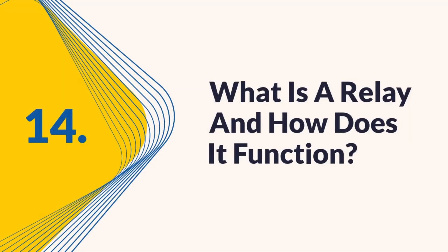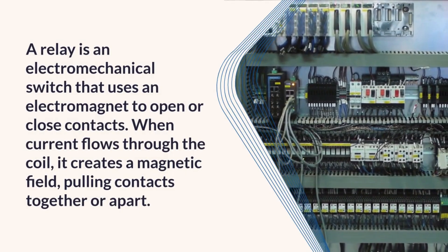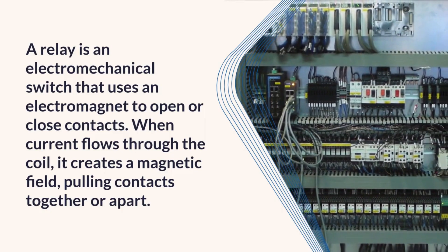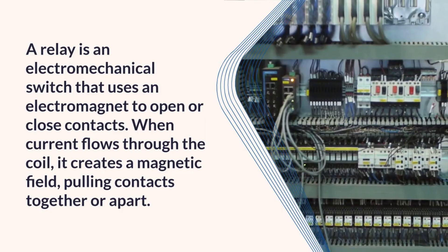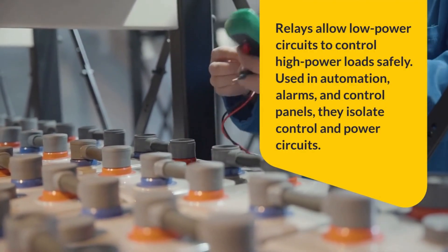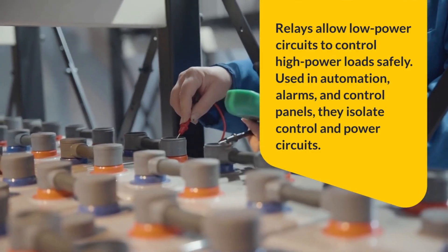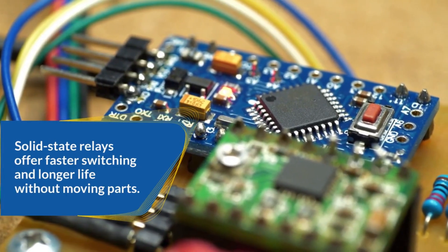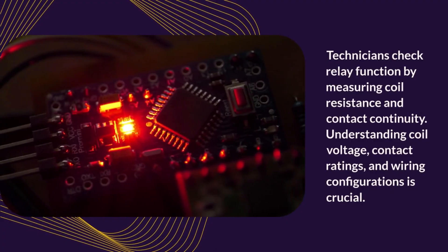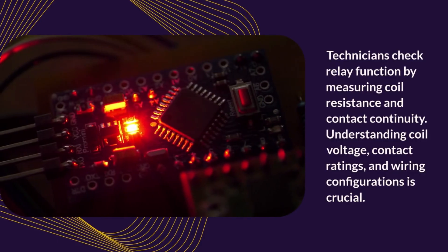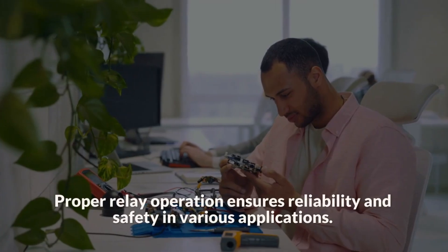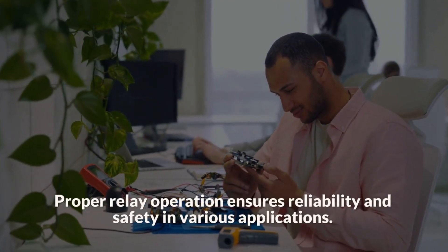Question 14: What is a relay and how does it function? A relay is an electromechanical switch that uses an electromagnet to open or close contacts. When current flows through the coil, it creates a magnetic field, pulling contacts together or apart. Relays allow low-power circuits to control high-power loads safely. Used in automation, alarms, and control panels, they isolate control and power circuits. Solid-state relays offer faster switching and longer life without moving parts. Technicians check relay function by measuring coil resistance and contact continuity. Understanding coil voltage, contact ratings, and wiring configurations is crucial. Proper relay operation ensures reliability and safety in various applications.